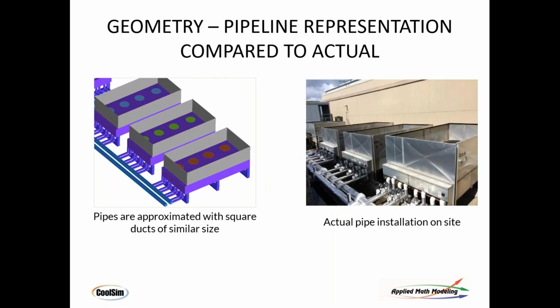We also do detail, like in this particular design, there's a lot of piping going in there. Well, guess what? That's going to affect, you can see right there, the percent area open for those inlets is being constrained by the geometry. There's not a lot of holes over there. It can pull from this side, but it can't pull from over on this side. So we try to represent the geometry as best we possibly can.